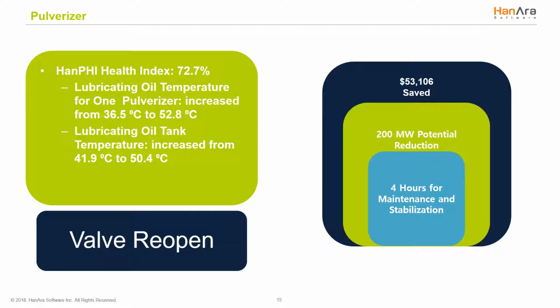After receiving HanPHI notifications, the Centralized Monitoring and Diagnostics Center immediately notified the site of the increasing temperature. After pulverizer maintenance, the site had closed the cooler outlet valve to rapidly increase the temperature, but forgot to reopen the valve once the lubricating oil temperature reached the desired temp. The site immediately adjusted the valve after receiving the early warning and was able to prevent a pulverizer trip that resulted from an operator error.